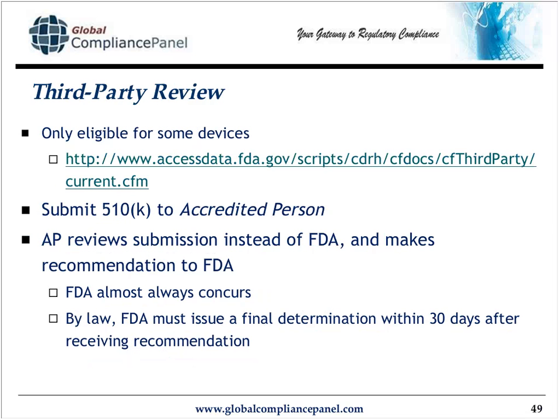I mentioned earlier, very briefly, the concept of the third-party review. It's not eligible for every single device out there, but it is eligible for quite a few of them. In this case, when I have my 510K, I'm not going to submit it to FDA. I'm going to submit it to what's called an accredited person. And the accredited person reviews the submission instead of the FDA because the FDA has licensed them, has authorized them to do this.